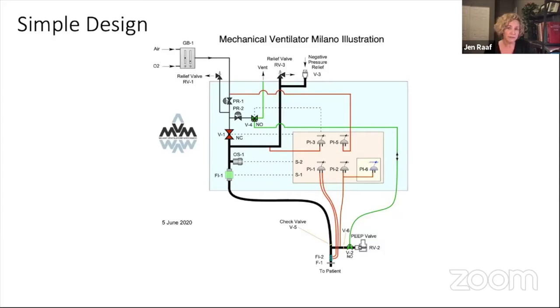If that isn't available, in the absence of a wall hookup, you can use a portable tank of pressurized air or oxygen. Starting at the top left of the image, you see where the air and oxygen enter this thing called GB1—an off-the-shelf gas blender that lets you adjust the fraction of oxygen the patient breathes. Normal air we're breathing right now is only 21% oxygen, but sometimes it's useful for patients with respiratory problems to breathe air with a higher oxygen fraction, and that's what this blender allows.